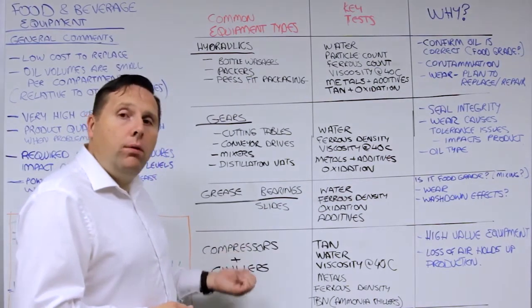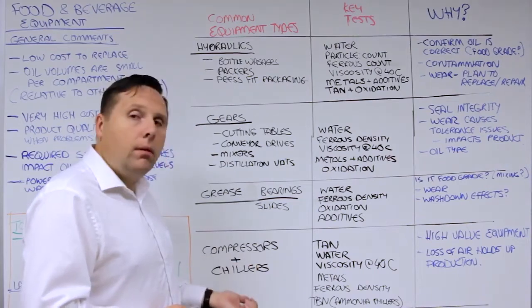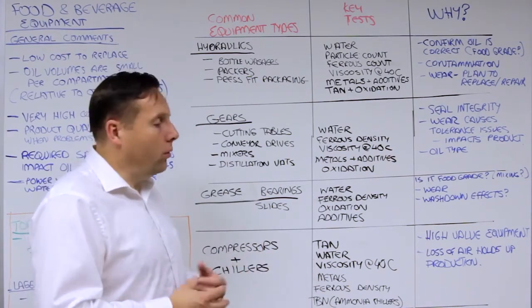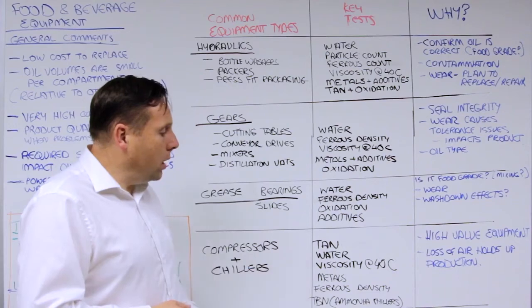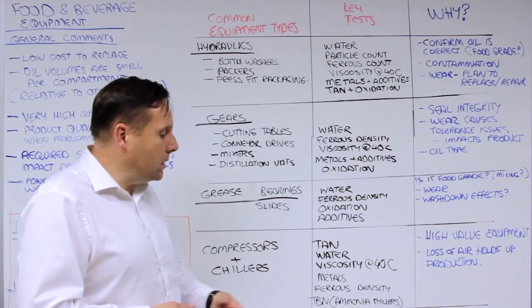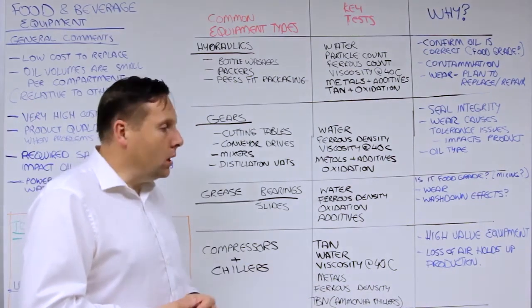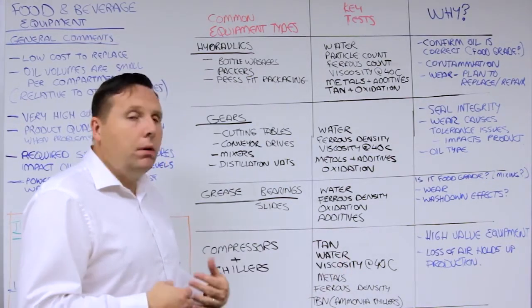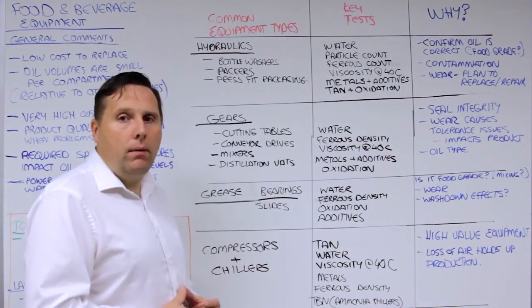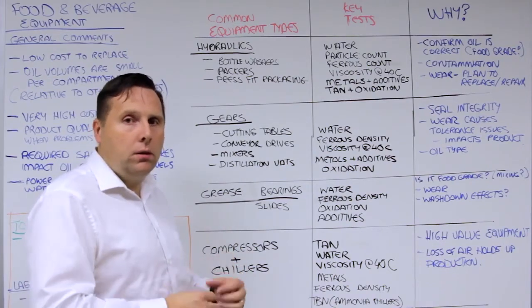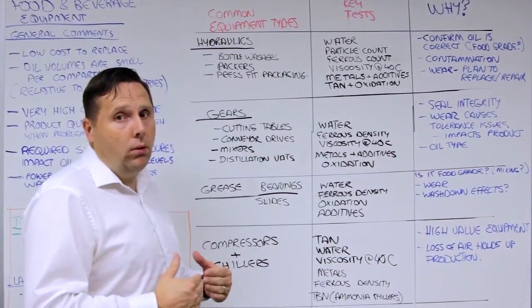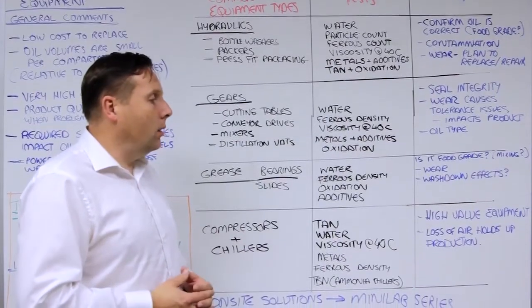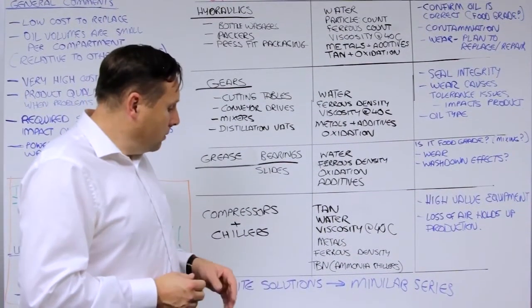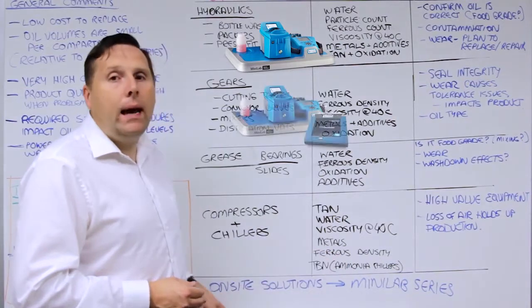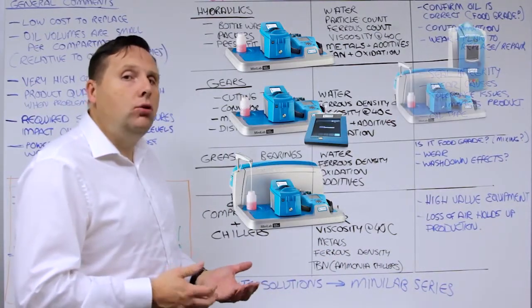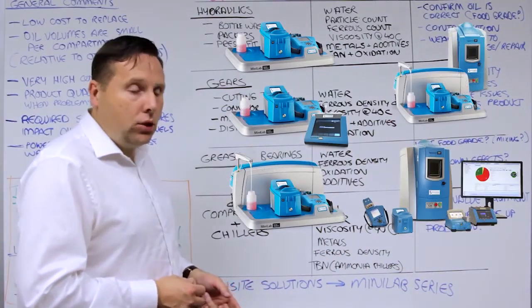And then, of course, the fourth utility in almost all these sites are compressors and chillers used for both cooling and, of course, air. Acid number, water content, viscosity, metals, ferrous density, and TBN if it's an ammonia chiller are all of concern. Our big worry there is those are actually the high value pieces of equipment in these sites. They're like the power utilities on the side. So we are worried about those, and any interruption of service can cause a major production loss. So as a result of that, we will always look at the Mini Lab series as a solution to try to address some of these issues.